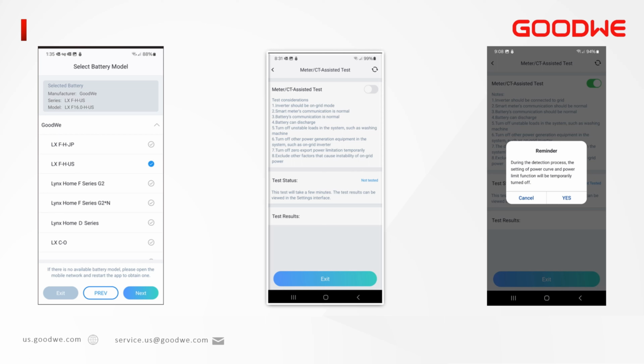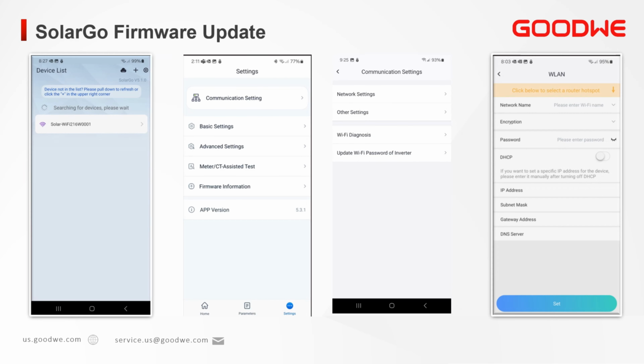If you're using Lynx batteries, did you remember the battery terminal resistor on COM2? Are your communication wires connected on the correct port for the type of batteries? Remember that the GoodWe Lynx and the BYD and LG have different connection points. Next, if you are not going to use CTs, you simply skip the steps, or if you are using them, then you need to enable by clicking yes. Now you will notice a waiting for test message and then click exit to finish.